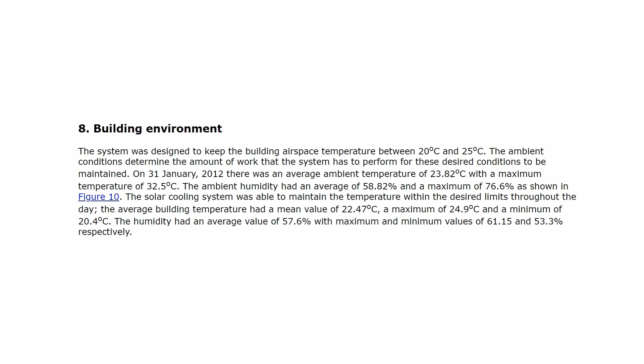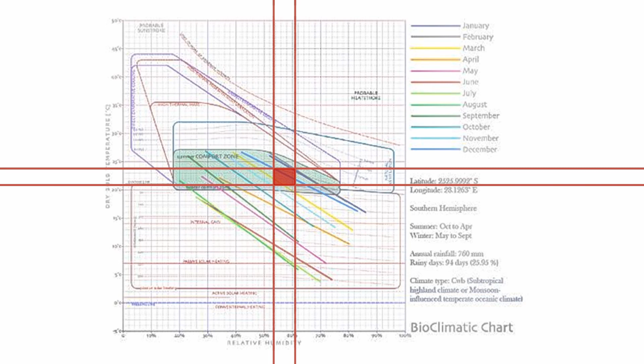The study found that the solar cooling system successfully maintained the building's temperature within the desired limits throughout the day. The average building temperature was 22.57 degrees Celsius, with a maximum of 24.9 degrees Celsius and a minimum of 20.4 degrees Celsius. The humidity levels averaged 57.6%, ranging from a high of 61.16% to a low of 53.3%. Based on the psychrometric charts of Midrand, the comfortable temperature zone is between 20 degrees Celsius and 27 degrees Celsius, indicating that the building's temperature consistently remains within the thermal comfort zone.